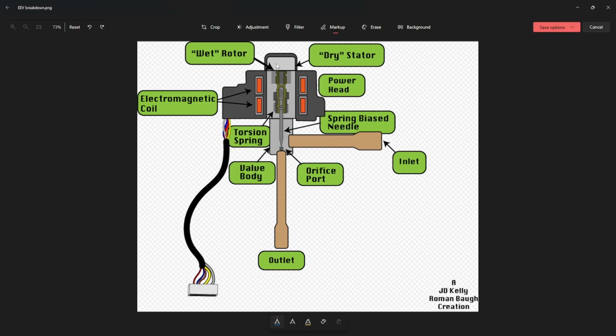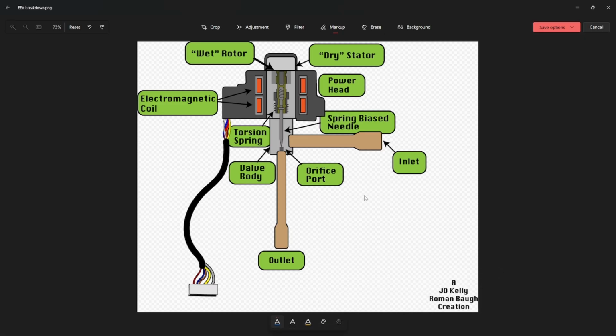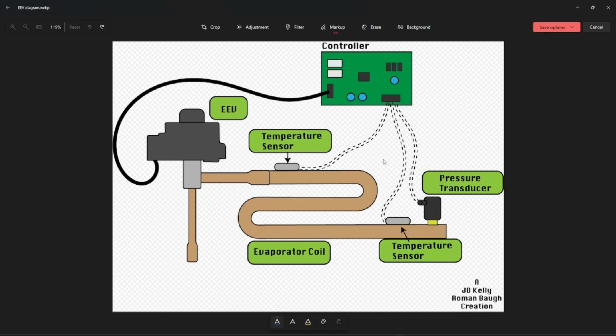Okay, so we've talked about resistance readings, what they're supposed to be. We've talked about how the EEV works, how to test for a restricted valve body, how to do the open-close test, the evap temp sensor, the gas temp sensor, what a pressure transducer is and how it works, what applications you would expect to see it in. I think for the most part, that about wraps up EEVs. So, I mean, they're a little bit different. They're not quite as simplistic as a TXV is, but again, it does the same job.